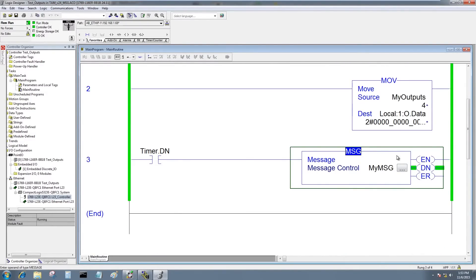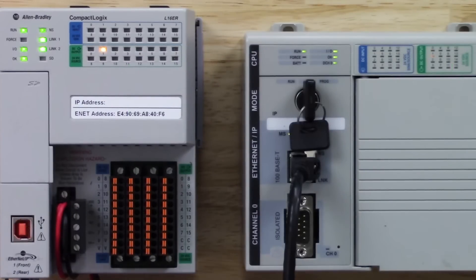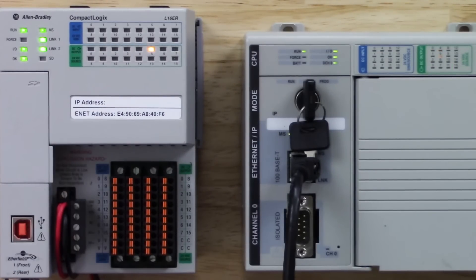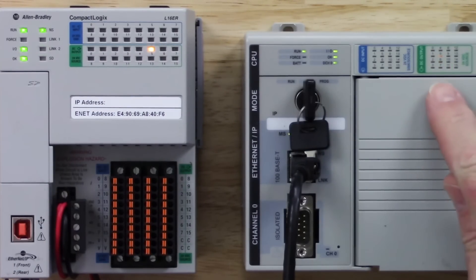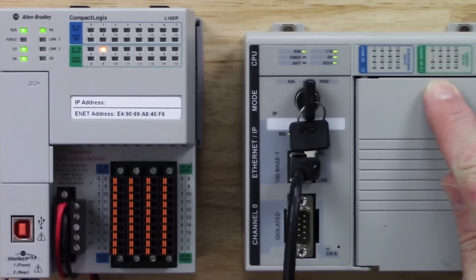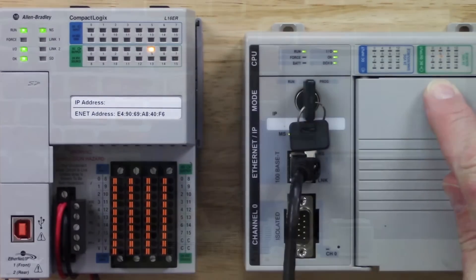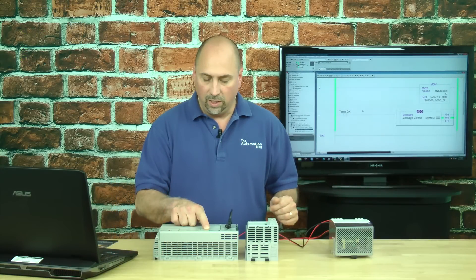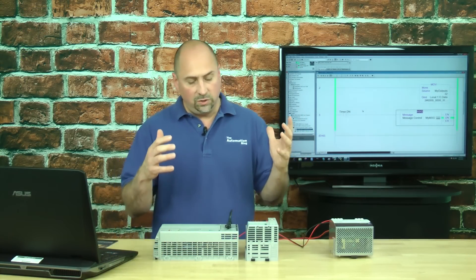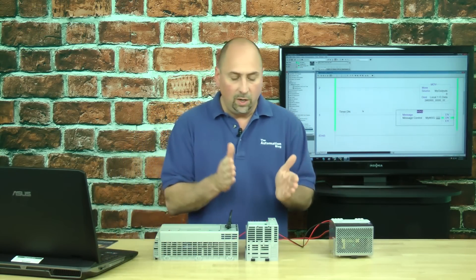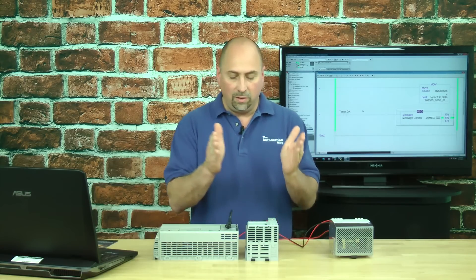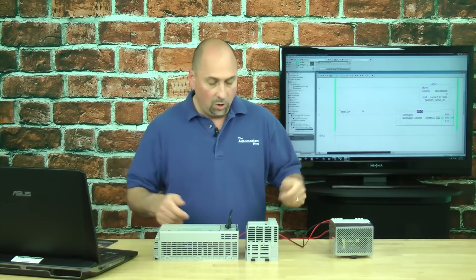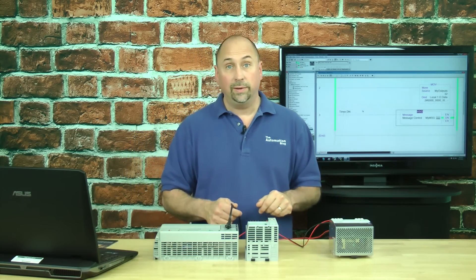And now you can see my outputs changing here on my L16. And hopefully that data is being messaged over to my L23 every time the timer is done. So let's look over here. We can see on the L16 we have the lights changing. And over here we have the same exact pattern. Zero through seven and back to zero. And that's how simple it is to message from your CompactLogix to another CompactLogix over Ethernet.